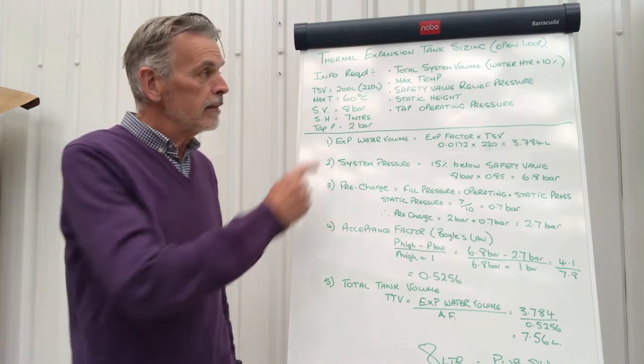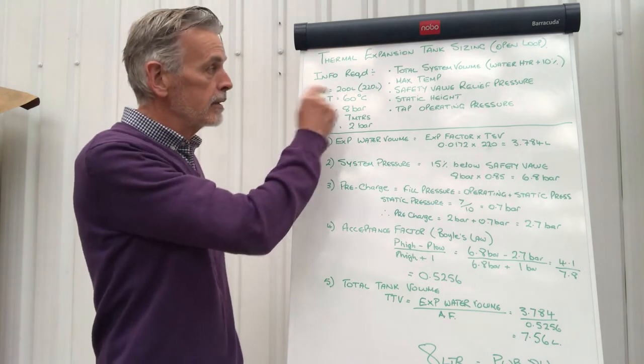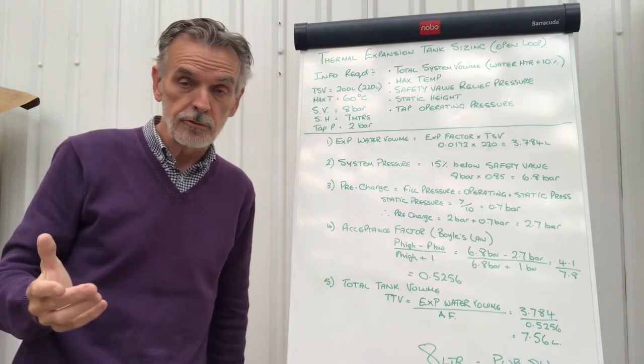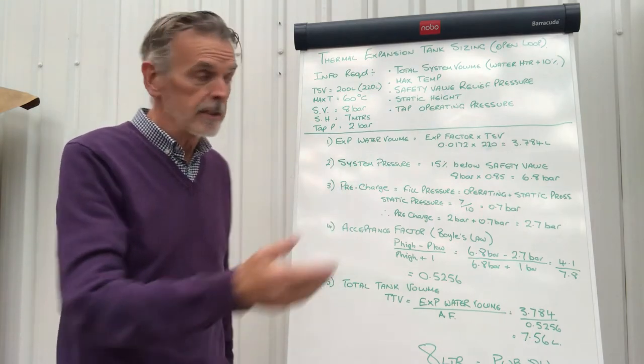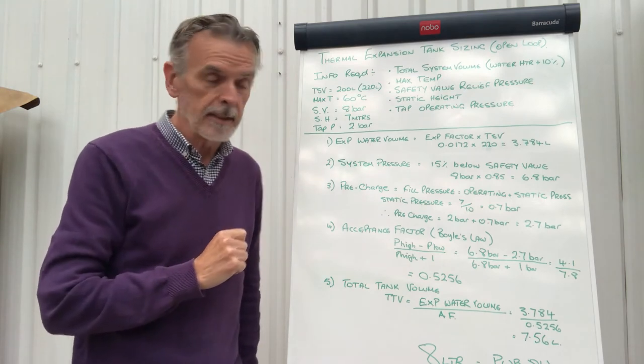So here are some parameters that I'm going to use for this calculation. The total system volume, the calorifier or unvented cylinder is 200 litres, so therefore 200 litres plus 10% equals 220 litres. The maximum temperature is 60 degrees centigrade.